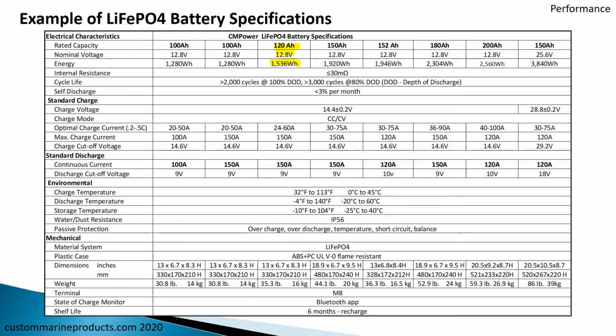They'll discharge less than 3% a month. And then we have our charge voltage, and a key factor here, an optimum charge current, which is between 0.2 and 0.5 C. So for a 100 amp hour battery, 0.2 would be 20 amps to 0.5 C, which is 50 amps. So the charge current that these batteries will take is pretty big, pretty significant. So you can pour a lot of power into these very quickly.